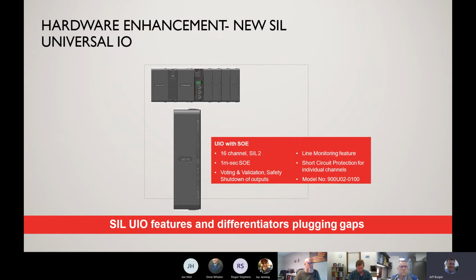The enhanced new SIL Universal I/O is really a differentiator out in the market. This offers 16 channels, SIL 2 rated, with a 1 millisecond scan time. You can do voting and validation for safety shutdown applications, line monitoring features, and short circuit protection for individual channels. Each one of the channels is isolated from the others, so if one channel fails, it doesn't jump over to all the other channels and fail the entire card. This can be configured for multiple universal ins and outs on a single card. So instead of ordering two separate cards, one for inputs and one for outputs, you can use just this one and do it all on one board. This reduces a lot of additional I/O that you might have to order for your project.